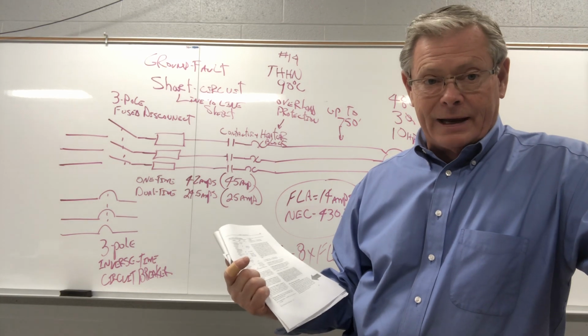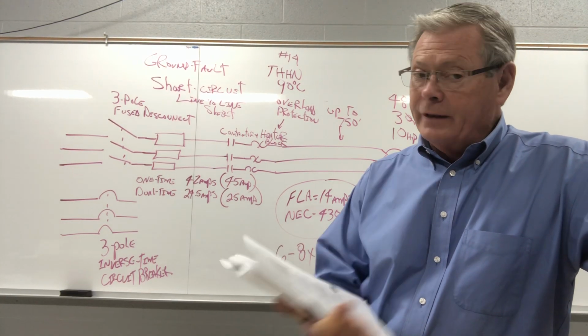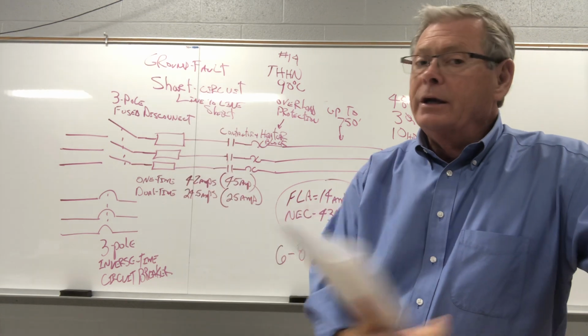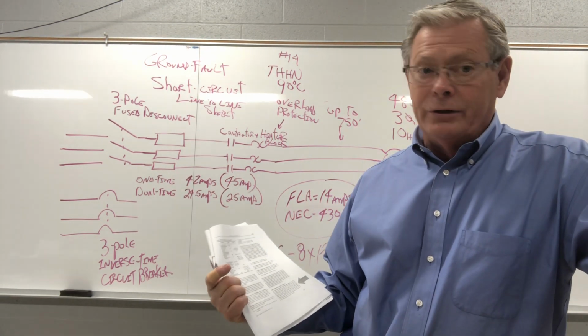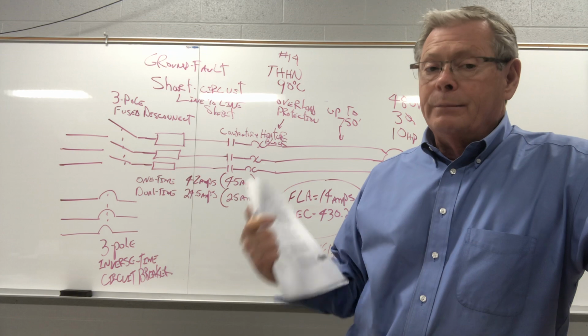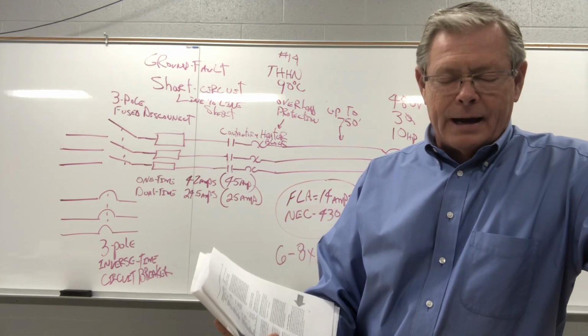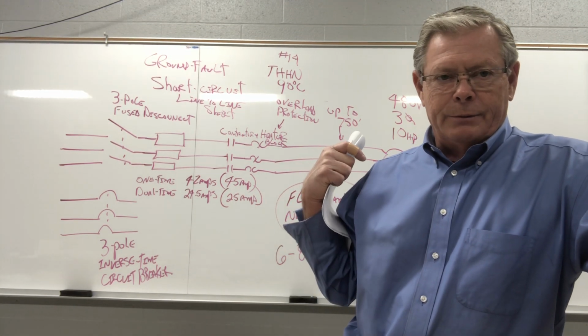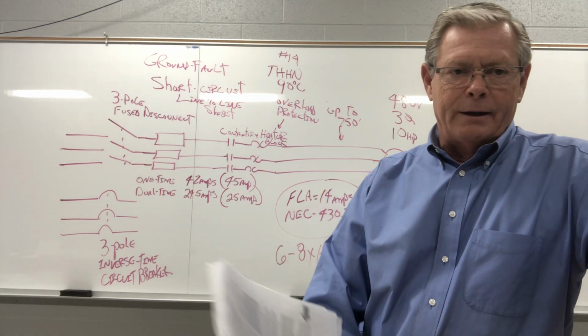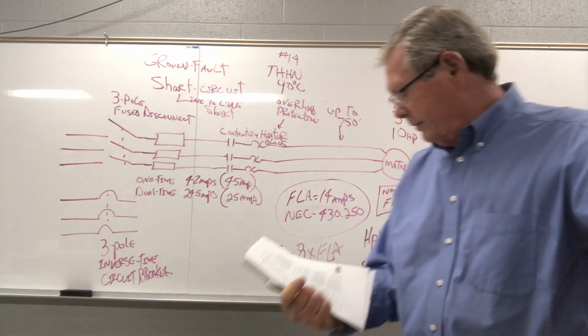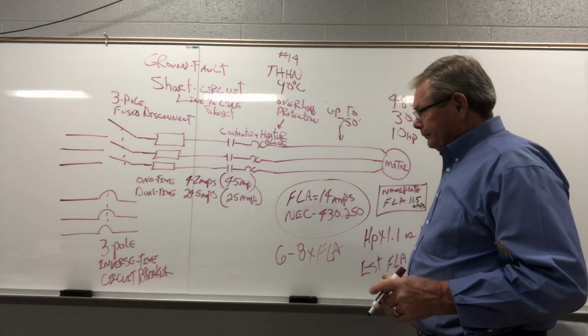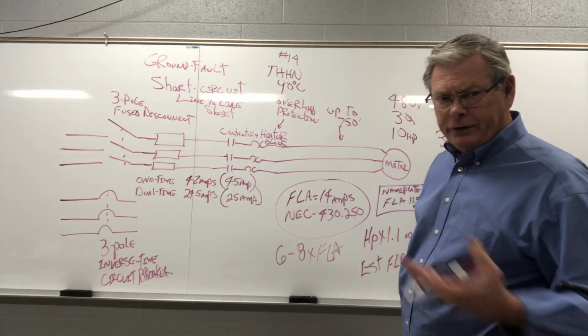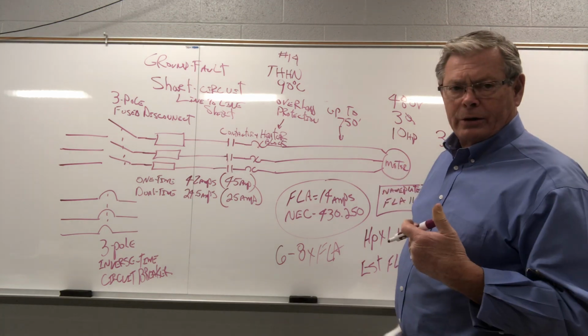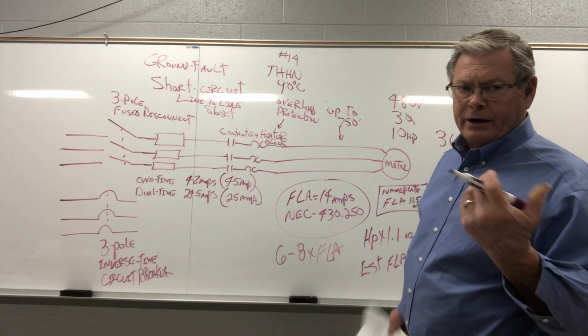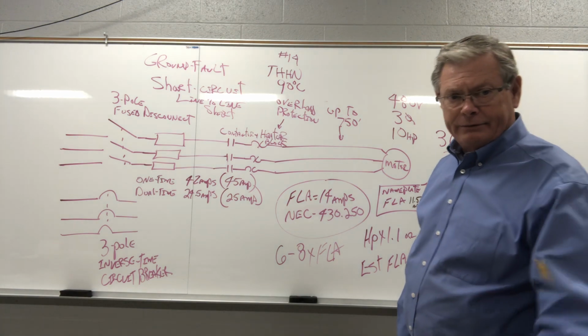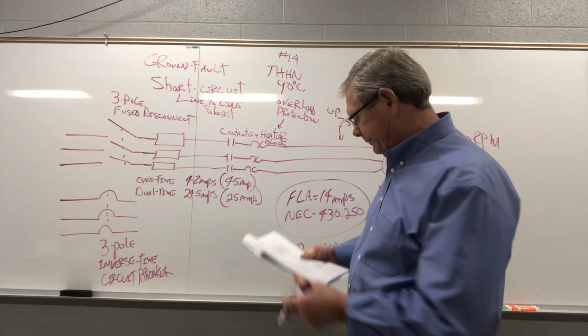Now, you're going to find everything out there, but I'm telling you the right way to do it. They all have different time current curves. You should change them all out together, even though you have one or two good ones left. Put all three non-time delay in, and then when you get the dual element replacements in, change all three out and put 3 dual elements in. Right way to do it, okay? Now, let's say you have a circuit breaker instead of fuses. That's my favorite. You have a motor that goes to ground and trips your breaker. You can reset your breaker once you change your motor and you're in business. You don't have to go to the storeroom. You're not always buying fuses.